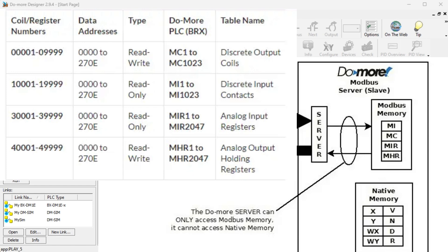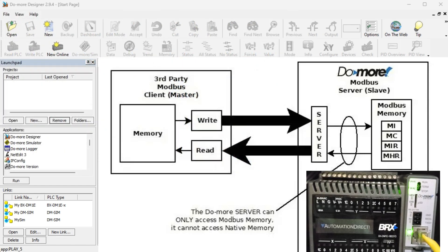In our example we will read and write 100 discrete bits of information and 100 registers. Using the Do More Modbus registers, we will read 100 MI discrete input contacts and 100 MIR input registers. We will also write 100 MC discrete output coils and 100 MHR output holding registers. This is all from the Modbus TCP client PLC, which is the PLC simulator.